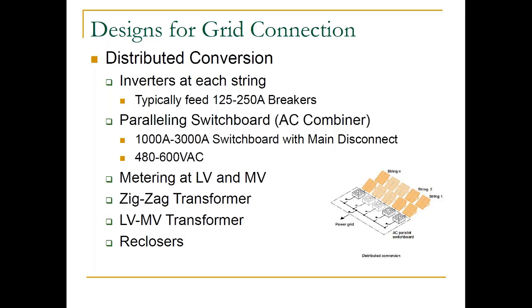In this case, there is 1 to however many strings of solar panels, mounted usually on a metal framework out in a field, that tie to inverters that will typically have a DC disconnect on the inverter itself to disconnect an individual string. And then those will step up to AC and parallel at the AC parallel switchboard. At States, we typically see these range anywhere from 1,000 amps up to 3,000 amps. It's driven by the number of strings that an engineer or developer has designed into the size of the equipment.